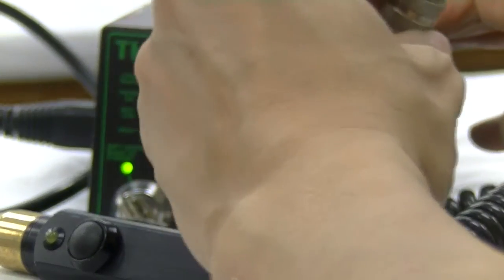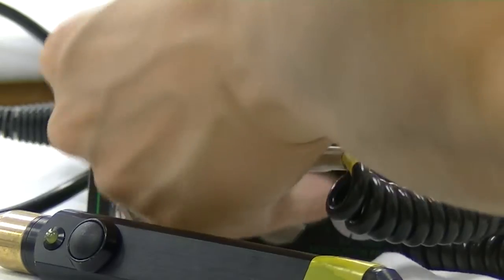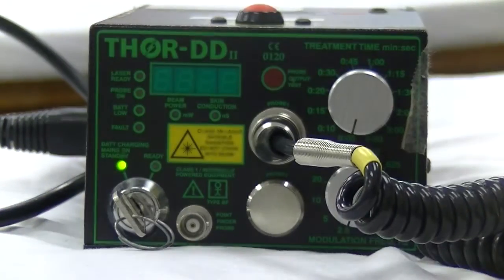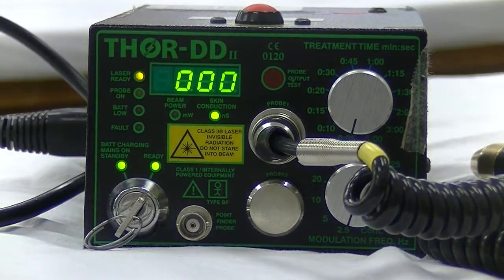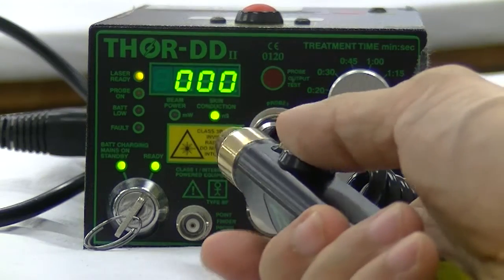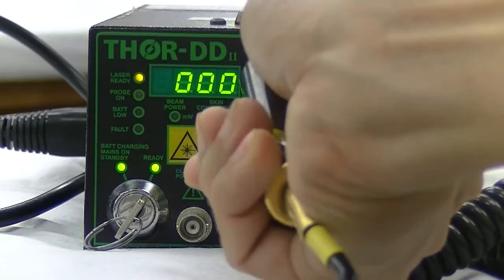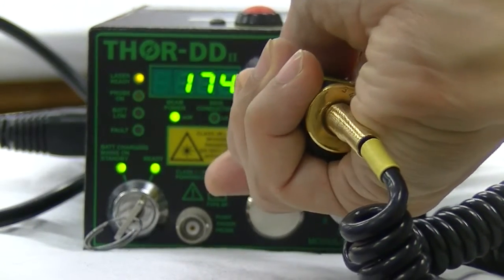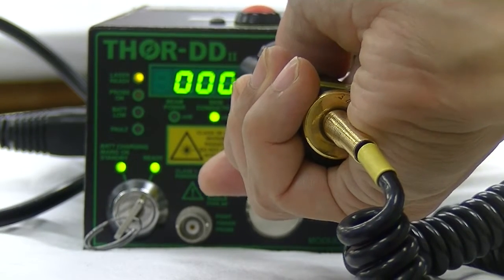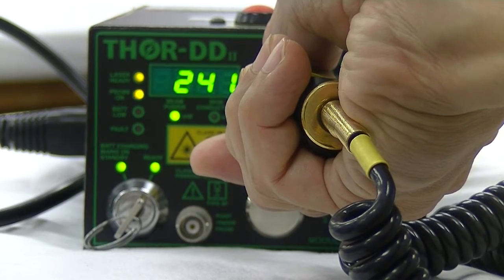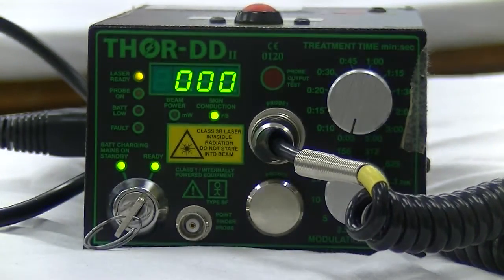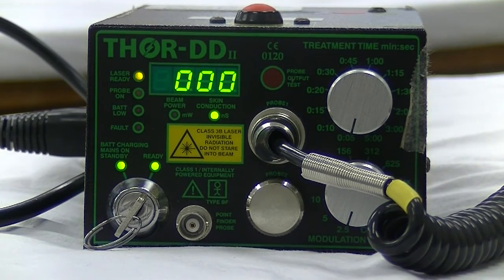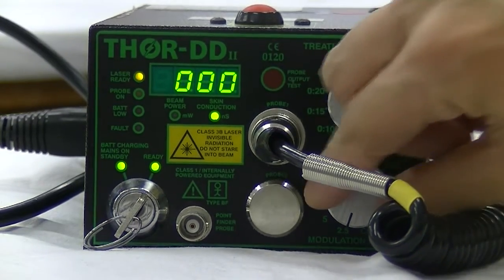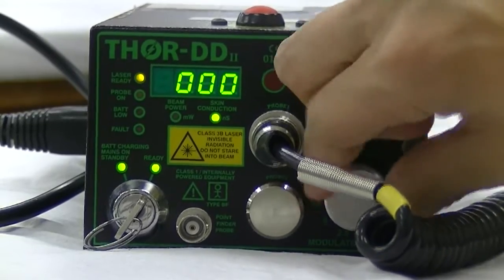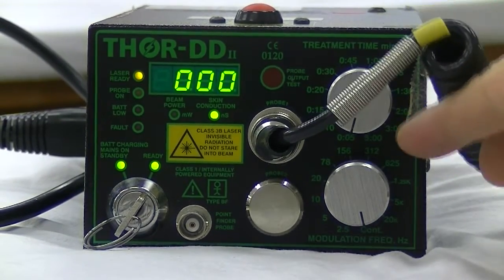So let me plug this in. Now I will start to turn the key to start the machine. Just like any machine, it will start with a beep. Before we start any treatment, remember we need to test the probe. So we put it at the testing area, press it, and you can see that it's delivering around 200 milliwatts. Let's do it again, around 200 milliwatts. Okay, now for treatment, for example, this time we have a continuous treatment again, so turn the knob for the frequency all the way to the continuous mode, right there.